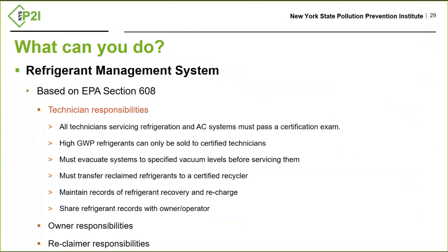So all technicians servicing refrigeration and AC equipment must pass the certification exam. High GWP refrigerants can only be sold to certified technicians. When working on a refrigeration system, the system must be evacuated to a specified vacuum level, and all of the refrigerant must be taken out and captured. And then any reclaimed refrigerant must be transferred to a certified recycler who can then purify it or destroy it, and if it's purified, resell it. The technicians must also maintain records of any refrigerant that they recovered or any additional refrigerant that they had to put in to recharge your system. And then they also have to share those records with the owner.